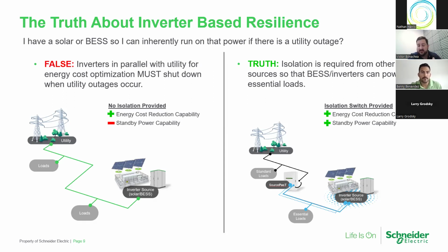So power is good, that isolation point is closed, and everything's operating grid tie. Power goes bad, that isolation point opens, the inverter provides power in grid forming, and your essential loads are back online. One other clarification point I just want to make here. I've given versions of this presentation a few times. There are utility and code requirements for disconnects and isolation points on the inverter for lockout, tagout reasons, for serviceability reasons. That is different than the isolation and the interconnect into the electrical system as shown here.